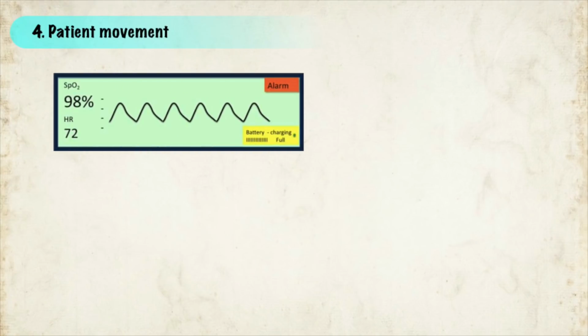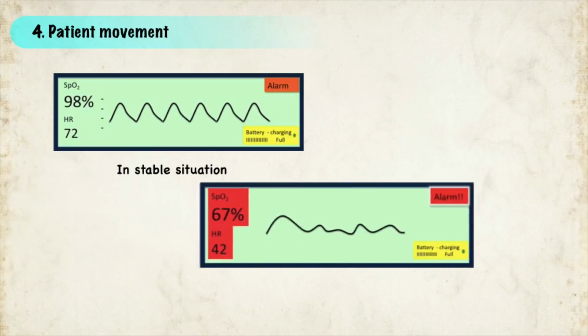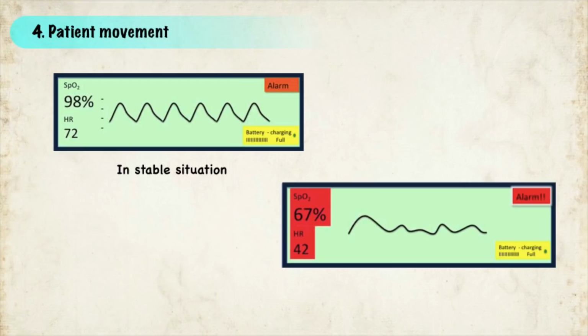Movement of the patient can also affect the final reading. Here is an oximeter attached to the patient. The SpO2 is 98% and pulse is 72 bpm. The trace shows a waveform with a regular pulse. What is the difference between this trace and the next picture? Notice the pulse waveform is erratic and not being well detected. This is the same patient but has now started shivering, which can result in an abnormal reading and cause confusion. So hold the hand steady or wait until the patient has stopped shaking and then recheck.